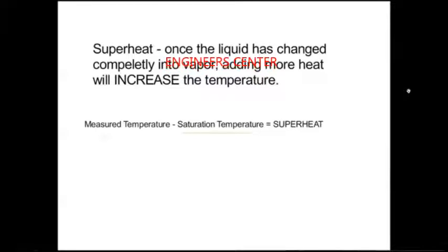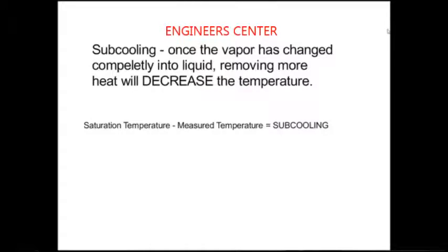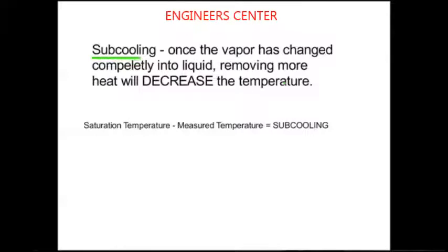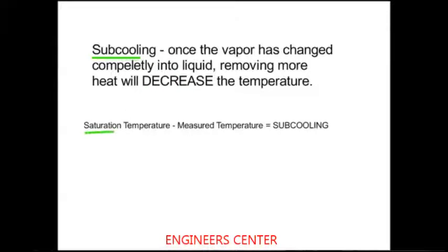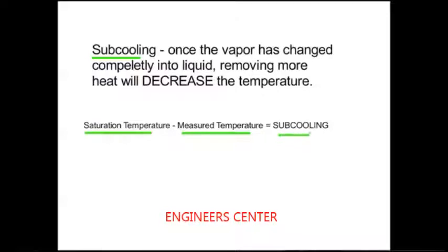Now, this has a lot to do with refrigeration troubleshooting, which we'll get into in another webinar, but superheat and subcooling are important. So subcooling. Okay, so once our vapors change completely back into liquid, and we're 100% liquid, removing heat will decrease the temperature. So we're removing sensible heat. So if you take your saturation temperature and then you measure the temperature of the liquid, the difference is subcooling.